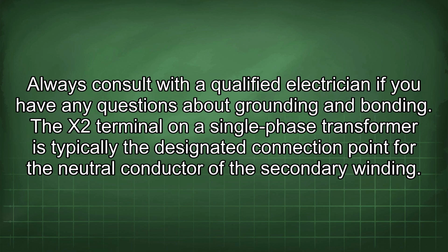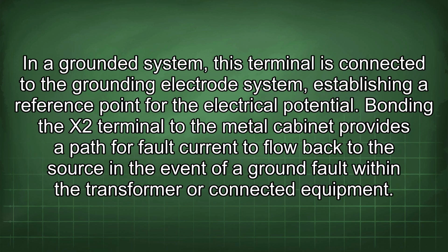The X2 terminal on a single-phase transformer is typically the designated connection point for the neutral conductor of the secondary winding. In a grounded system, this terminal is connected to the grounding electrode system, establishing a reference point for the electrical potential.